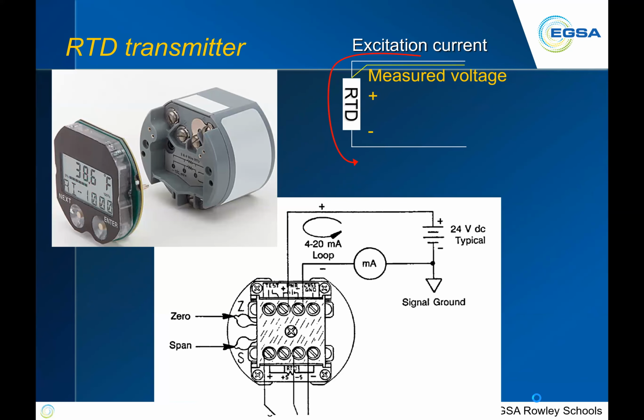Here's a transmitter that shows that RTD type of device. On the bottom graphic there, you'll see the 0 and the span. That's how you calibrate things. 0 is going to be your 0, obviously, whatever your low setting is. Span is going to be your high setting. So if it's a device that's going to meet a maximum of, say, 500 degrees, you would set that up for 500.